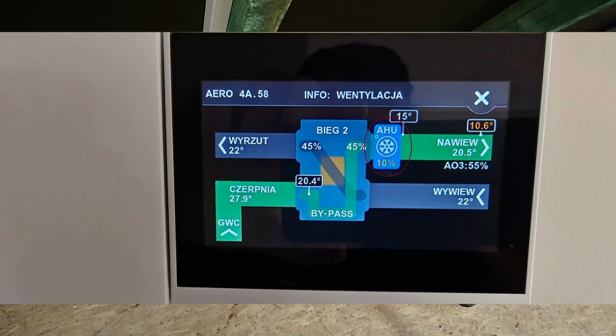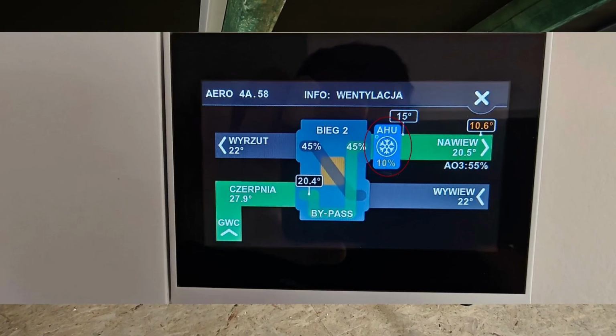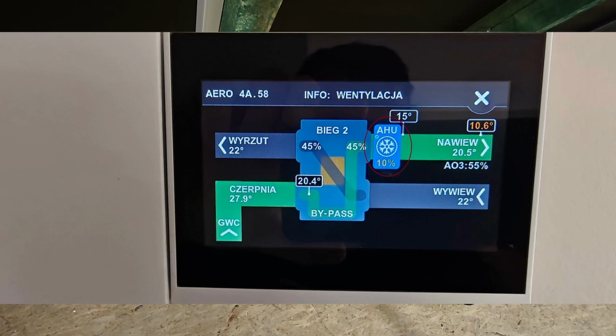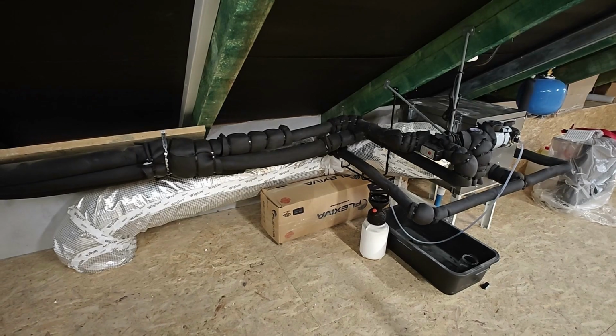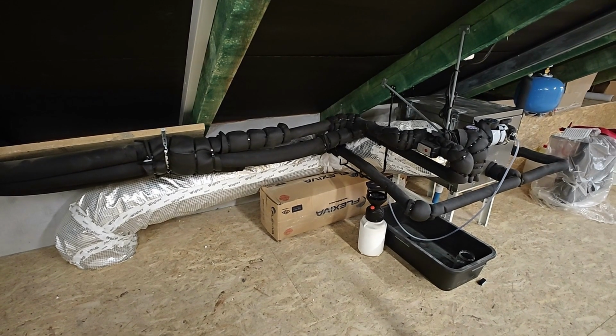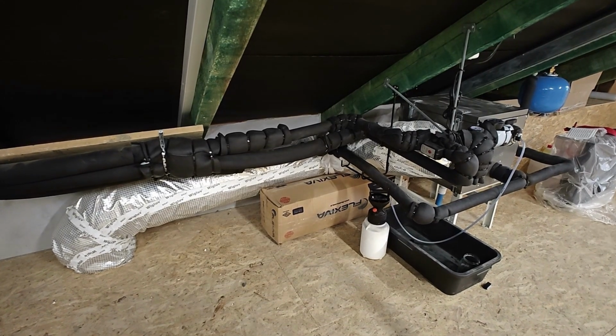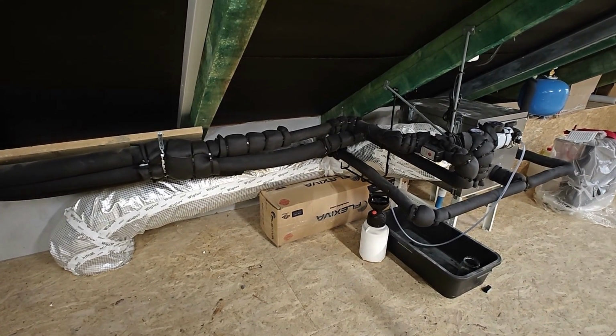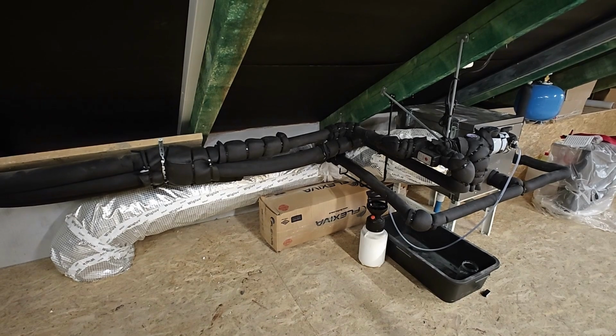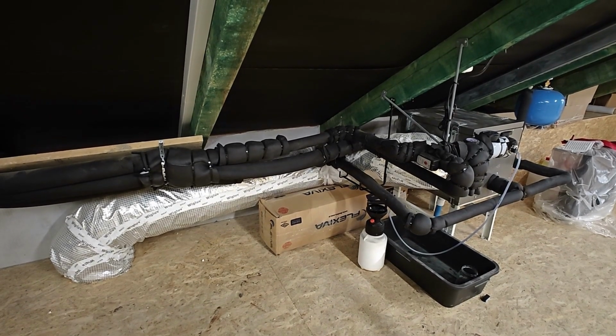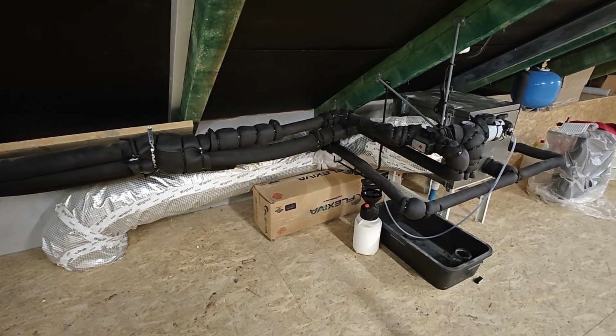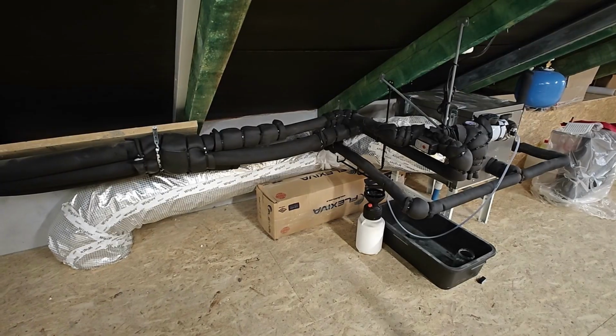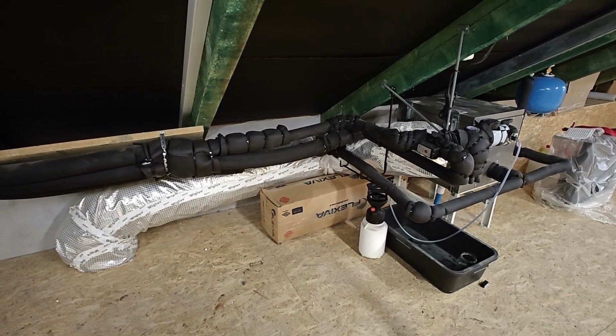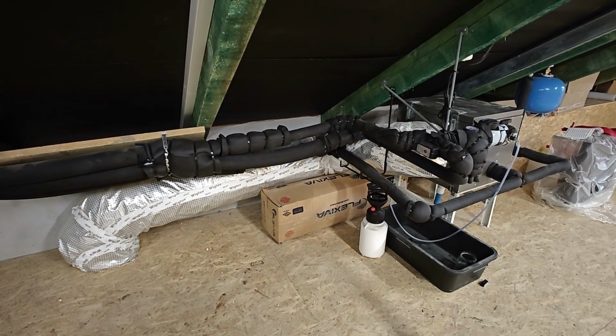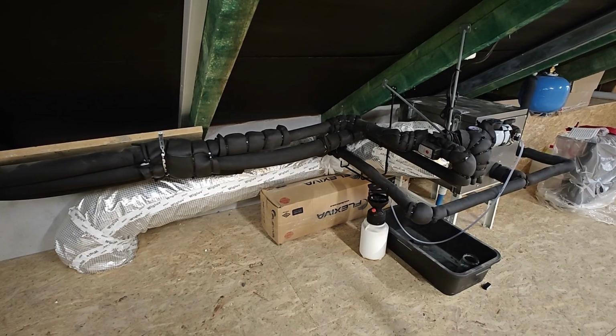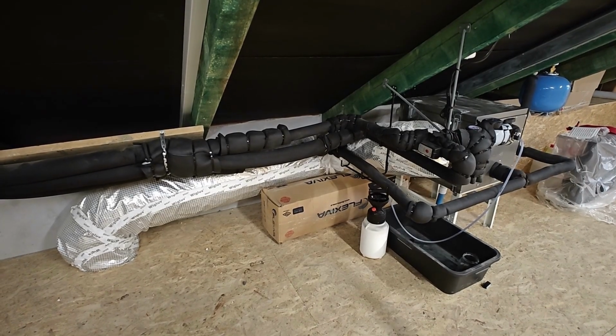If, say, a premise is to use air conditioning in the summer, powered by electricity, then these are also savings that must be taken into consideration. As for the operating costs of this system, at this moment, it seems to me that the only cost is that of the circulation pump, which in this case runs on the first gear and consumes about 5 watts. The system operates only when there is a clear justification for it, specifically when the temperature is above the set point when it needs to cool the air or when it needs to heat it. During transitional periods, it is switched off.